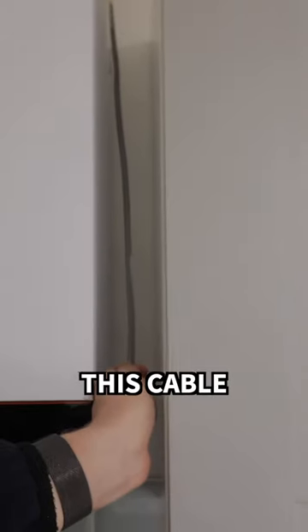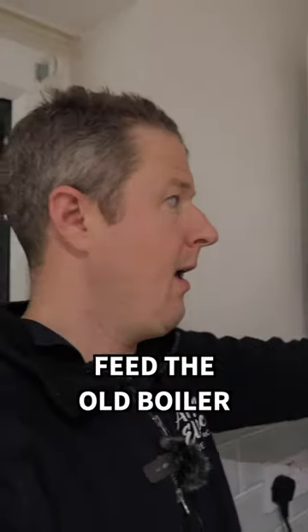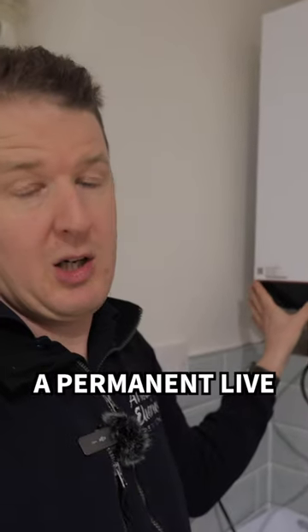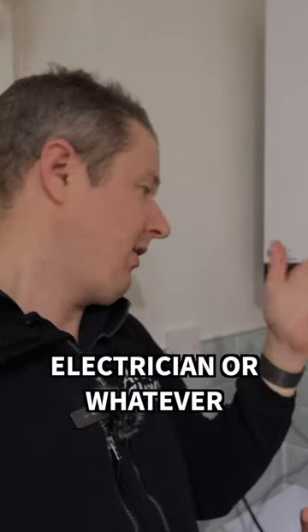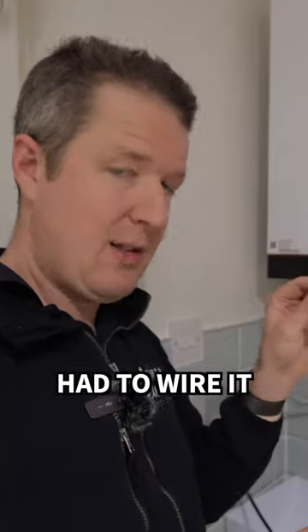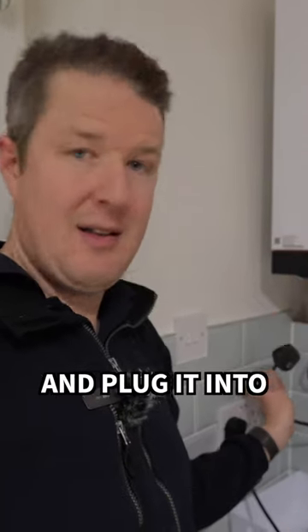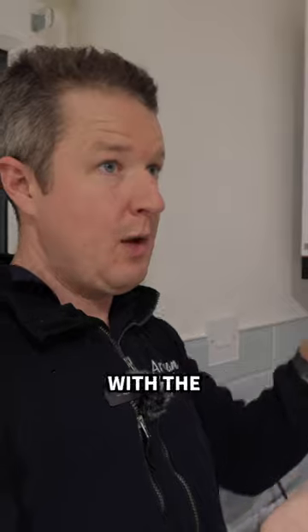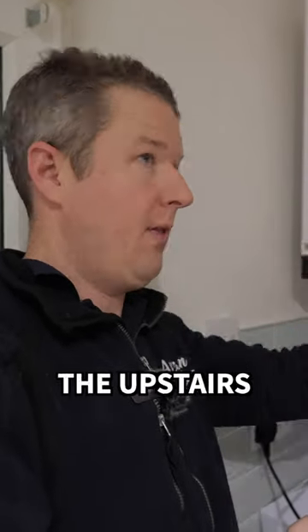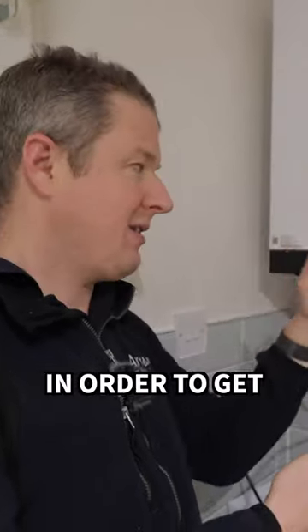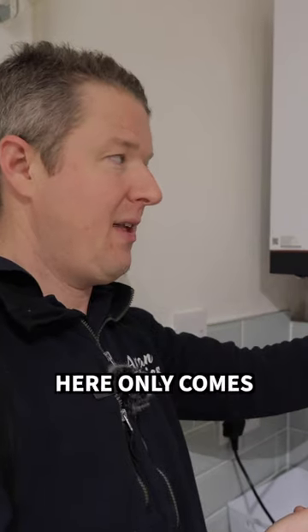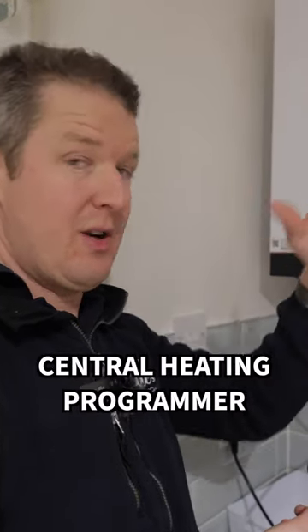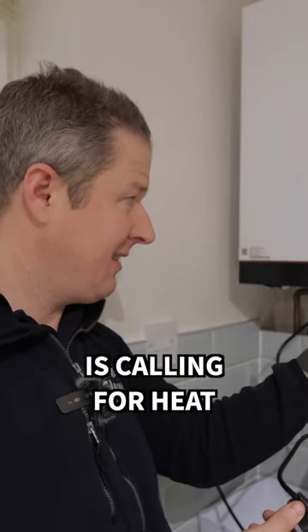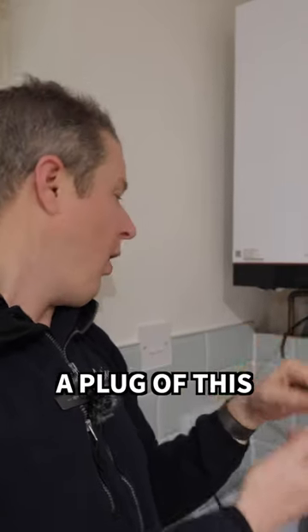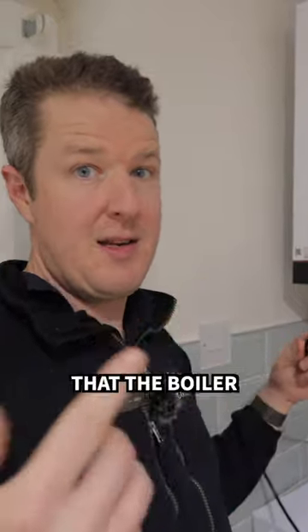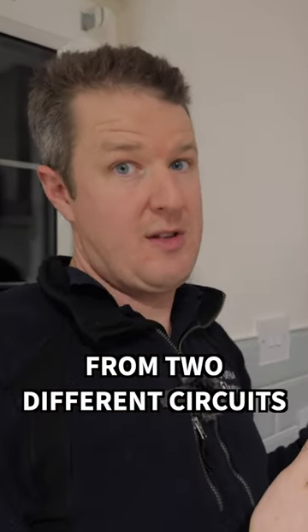This cable is what used to feed the old boiler, but because the new boiler needed a permanent live, the plumber or electrician who wired it up had to wire it off a plug and plug it into the socket. The old boiler, with the thermostat and everything, was wired off the upstairs socket circuit in order to get a permanent live, because this twin and earth here only comes live when the central heating programmer is calling for heat. They've actually had to wire it off a plug off this circuit, which means the boiler is actually wired from two different circuits.